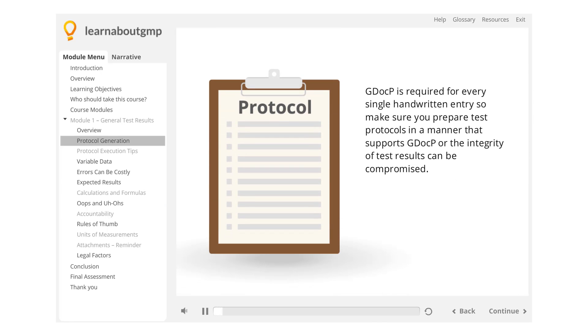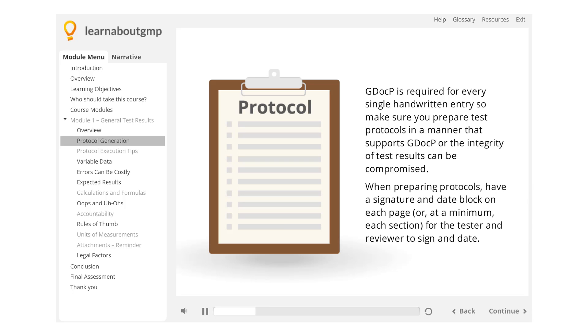GDocP is required for every single handwritten entry, so make sure you prepare test protocols in a manner that supports GDocP or the integrity of test results can be compromised.